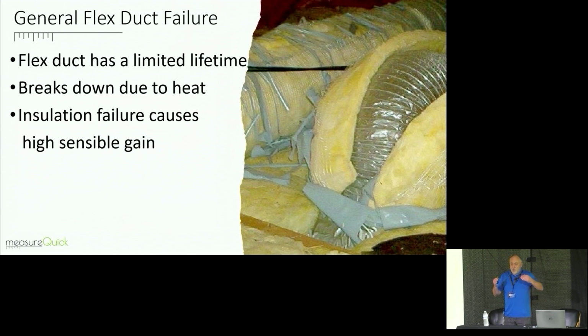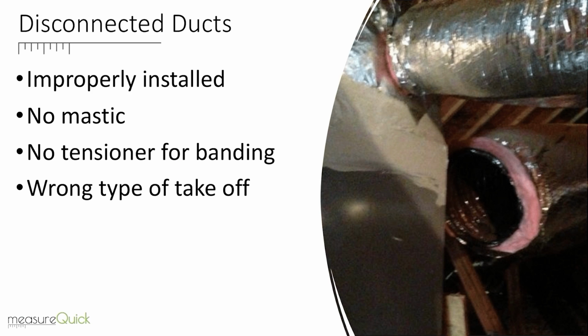People will put the probes out. When we're using MeasureQuick, we're going to test from inlet to outlet. I'll show you that in another slide. A lot of times we see low sensible capacity. And again, if you're not looking at the entire system, you're looking at this thinking the software must be wrong. You're going to blame something else when it's actually a duct system that's got high sensible heat gain.